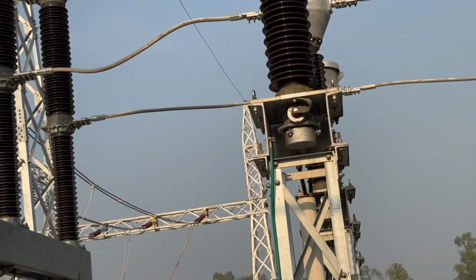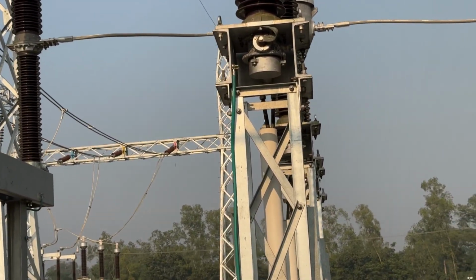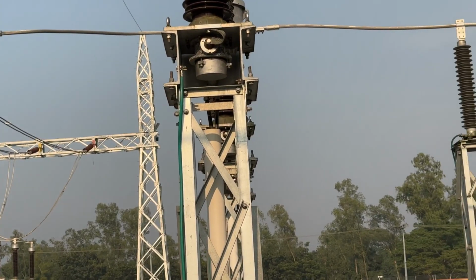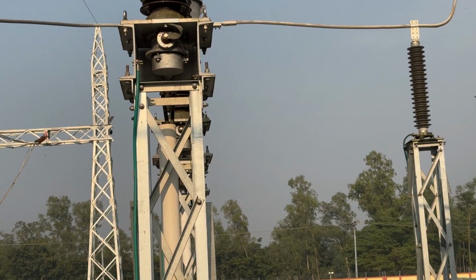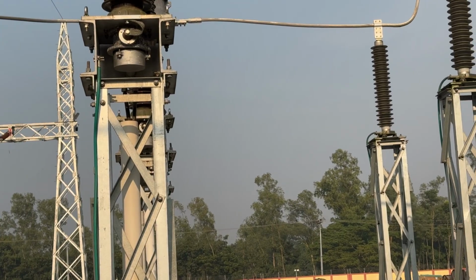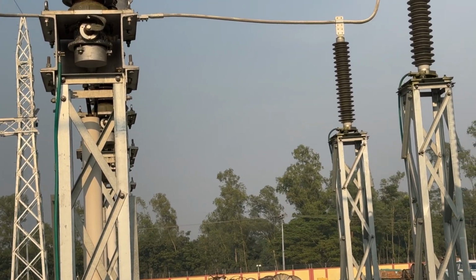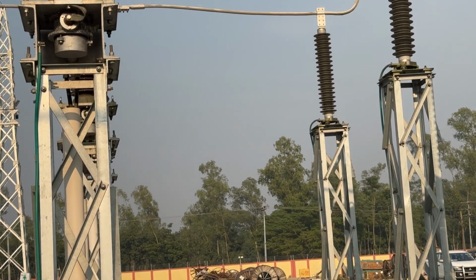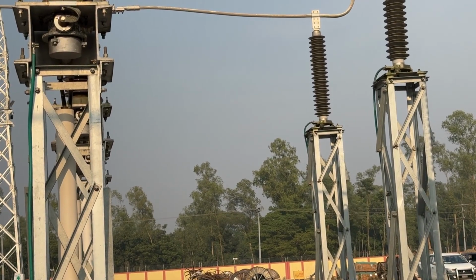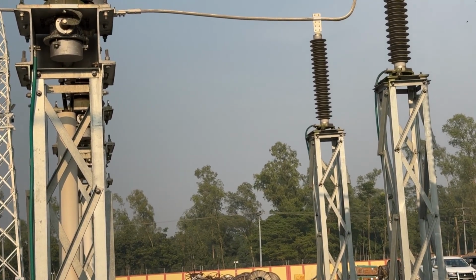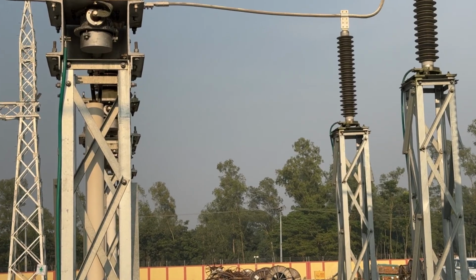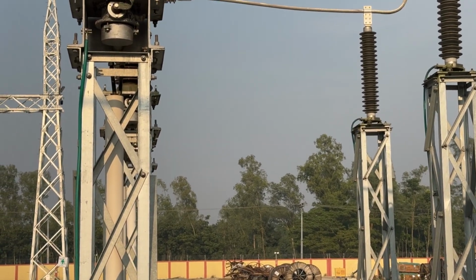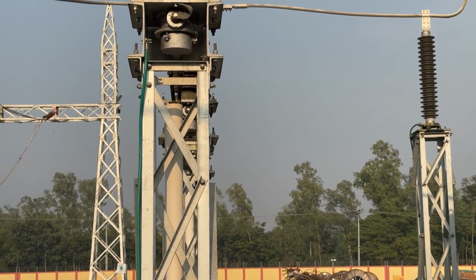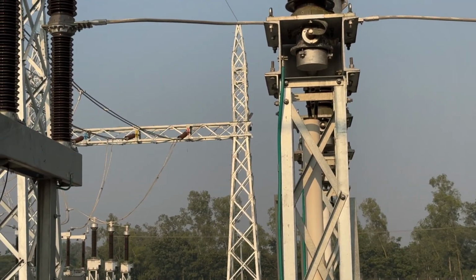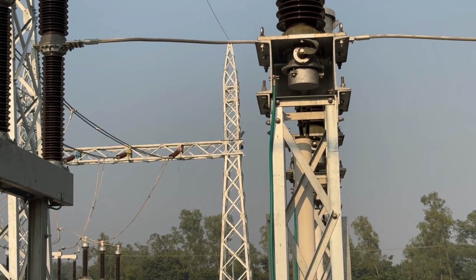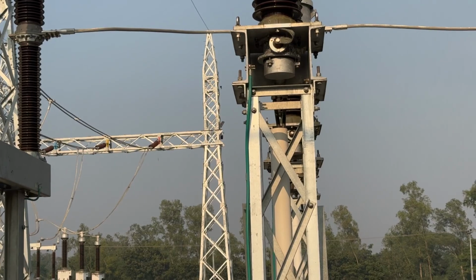We know that all the measuring equipment can measure either 1 ampere at full scale or 5 ampere at full scale. In earlier days there was a practice of using 5 ampere measuring equipment, but nowadays all the measuring equipment is based on a 1 ampere at full range system.